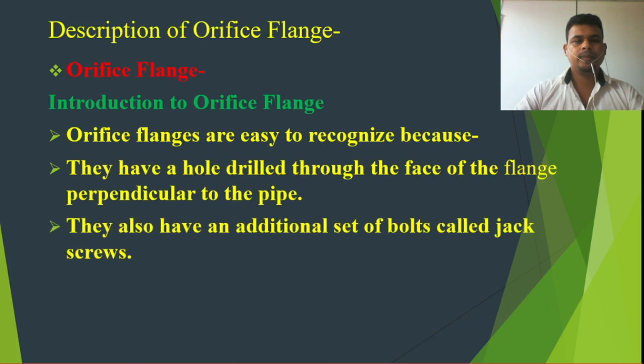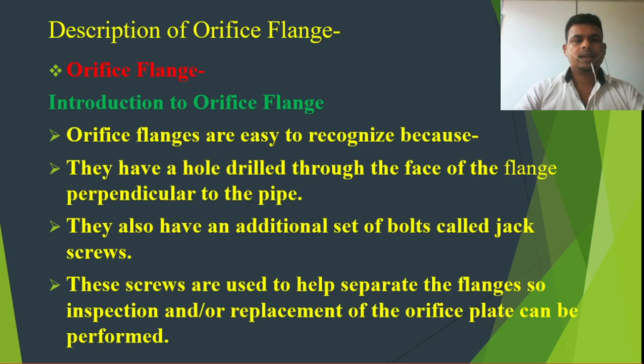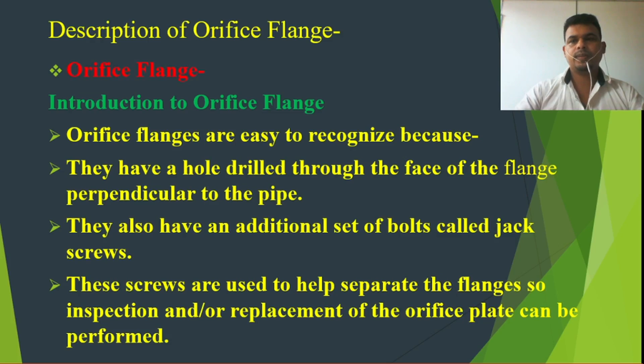The second thing is they also have an additional set of bolts called jack screws. These screws are used for a specific purpose — they are used to help separate the flanges for inspection and replacement of the orifice plate. So this jack screw is used for separating the flanges to replace the orifice plate.